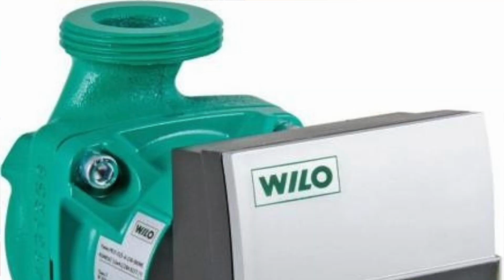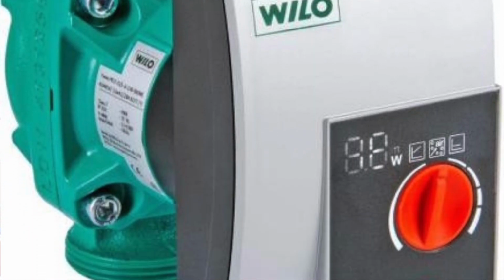Now Wilo, they've also got brand new sets of pumps with fancy settings on them and anti-seize and all the rest of the settings. So pumps have come loads of leaps since 2013, since we've had to start looking at the energy rating of pumps, because if your pump's too fast you're going to be using a lot of energy if it doesn't need to, so your electric bill's going to go up. Combi boilers, the speed of the pump costing people a lot of money, so they've got to reduce them and they work on the return temperature. But anyway, we'll go and have a look in boilers now and I'll explain more about the ERP pumps inside the boilers.